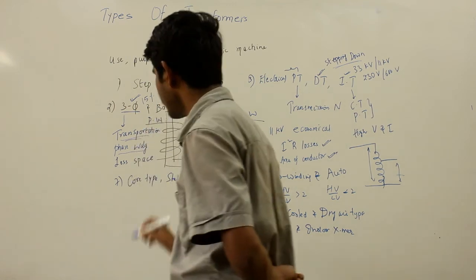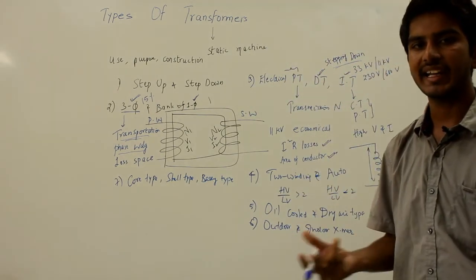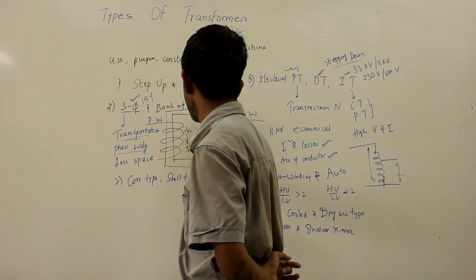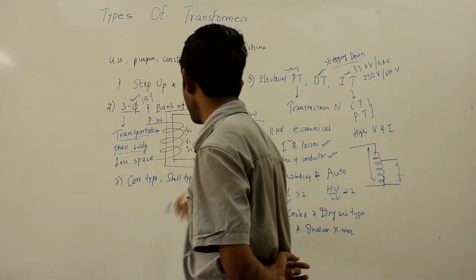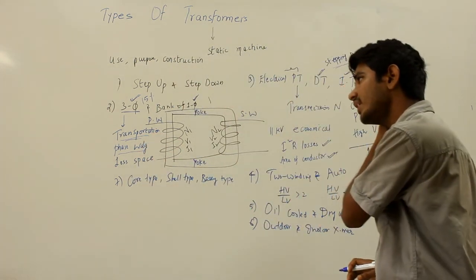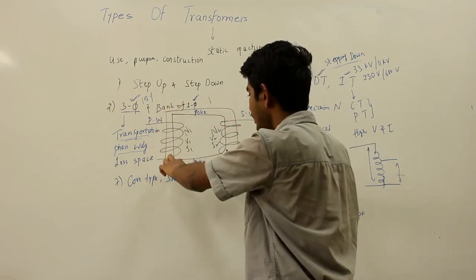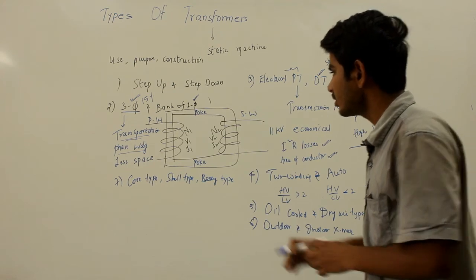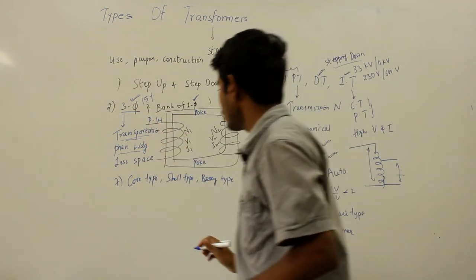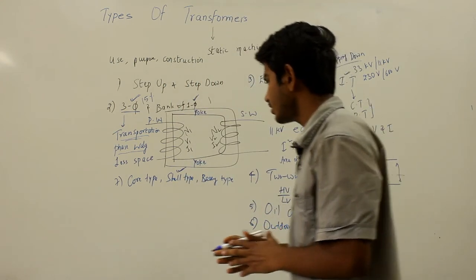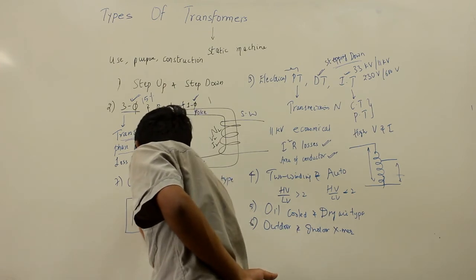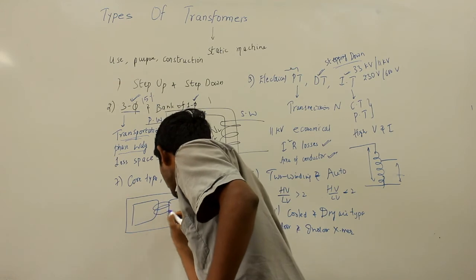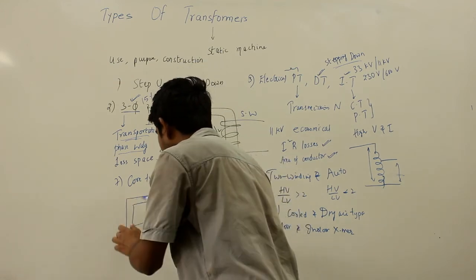The next type, based on construction, includes core type, shell type, and berry type transformers. The core type transformer has two vertical legs or limbs and two horizontal sections called yokes. The core is rectangular in shape with a common magnetic circuit, and cylindrical coils — both HV and LV — are placed on both limbs. The shell type transformer has a central limb with two outer limbs, and the HV and LV coils are placed on the central limb, providing a double magnetic circuit path.